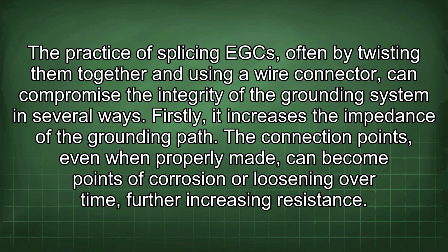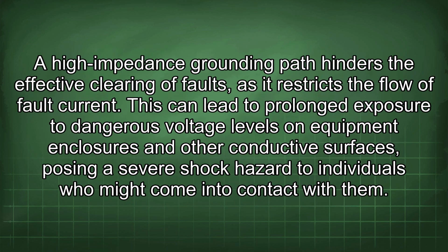The practice of splicing EGC, often by twisting them together and using a wire connector, can compromise the integrity of the grounding system in several ways. Firstly, it increases the impedance of the grounding path. The connection points, even when properly made, can become points of corrosion or loosening over time, further increasing resistance. A high impedance grounding path hinders the effective clearing of faults, as it restricts the flow of fault current. This can lead to prolonged exposure to dangerous voltage levels on equipment enclosures and other conductive surfaces, posing a severe shock hazard to individuals who might come into contact with them.